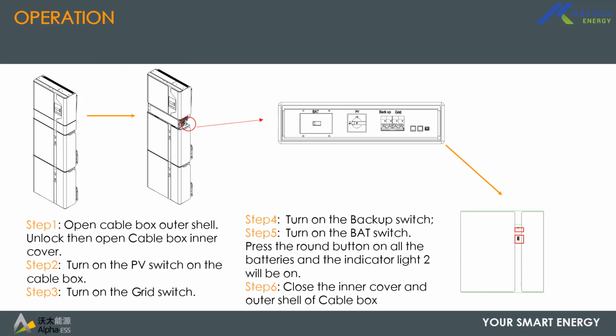For the power on procedure, you would first power on your PV array and put on your grid. One thing about this inverter, it's a hybrid inverter, and at the same time, it can be used as a grid tie inverter. So you can actually install the inverter without batteries and set it to operate as a grid tie inverter. The moment you power on your grid and PV, the inverter would power on. So if you use this as a grid tie inverter without batteries, then you'd need to set the battery ready. We'll look into it when going through the settings.